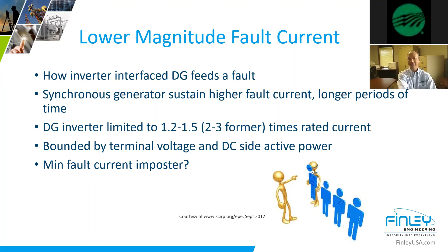How many of you have done distribution analysis and looked at your minimum fault currents because they act like cold load pickup? We have to be mindful of how we size our breaker devices because we don't want to do that. Solar inverter DG can act like a minimum fault current imposter, and you may not even be aware that that potential could exist. It could act like a cold load pickup because it's such a small contribution that we may not be protecting adequately against it.